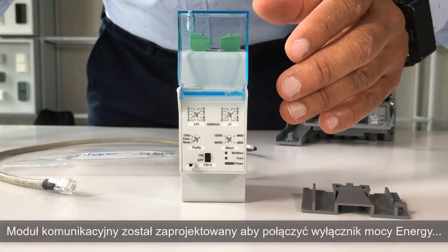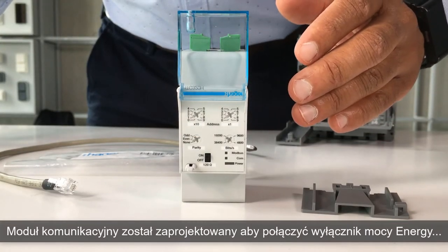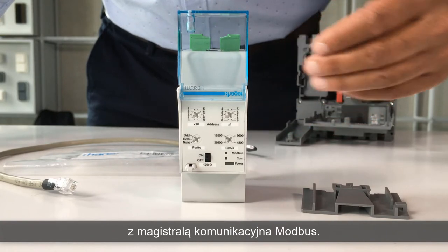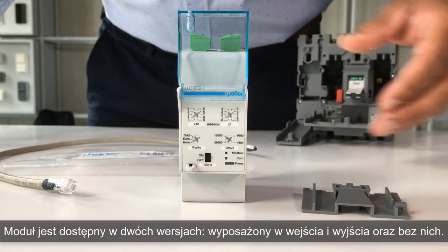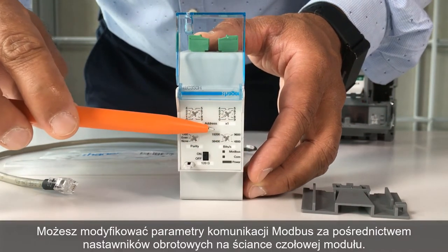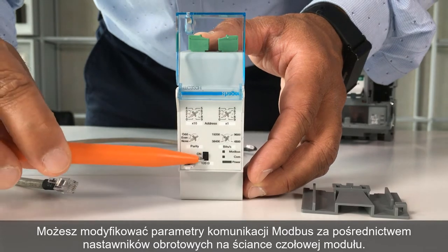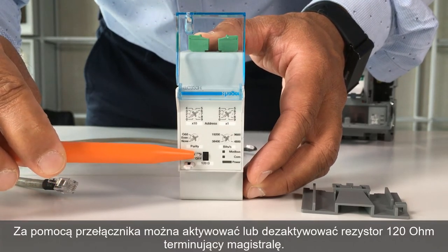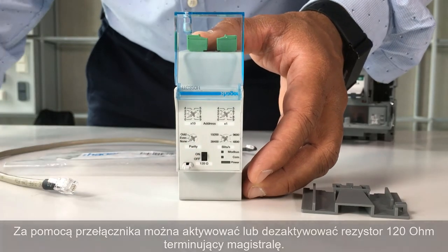The Modbus communication module is designed to connect the energy circuit breaker to a communication bus, which is compatible with Modbus RTU. There are two versions: with, or without inputs or outputs. You can modify the Modbus parameters with the adjustment dials on the front. With this selector switch, you can activate or deactivate the 120 ohms end-of-line resistor.